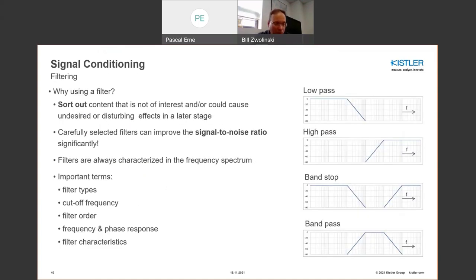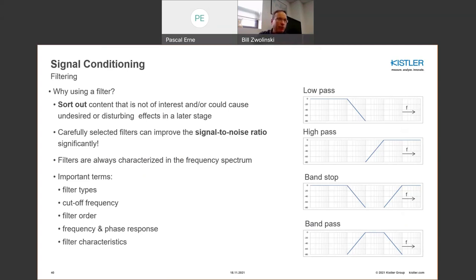Signal conditioning filters are always widely used, but my general recommendation for filtering is: try not to use it in the analog world. It's often best to take measurements wide open without any analog filtering whatsoever. The reason is that you're digitizing, and there's powerful software nowadays that can easily take that raw data and filter it digitally. This gives you the best chance of not distorting any signals — when you filter, you can very well distort the desired signal, attenuating what you're trying to measure. It's often good to measure wide open and then do your analysis in software.